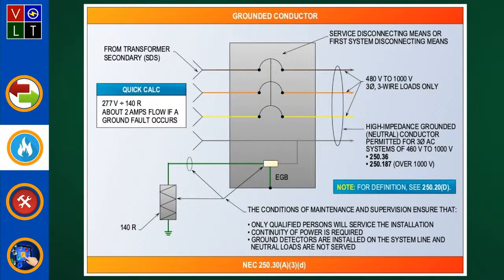We give you an example of how much current is going to flow with a quick calc. So if I had a 480/277 volt system, I'd take that 277 volts, and with a high impedance system set up there of 140 ohms resistance, you divide that in, and it tells you there's about 2 amps that flow if a ground fault occurs.